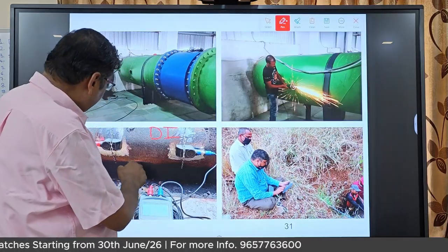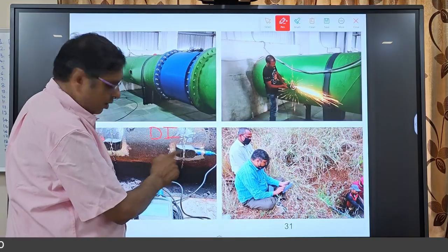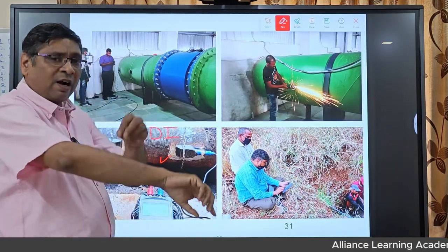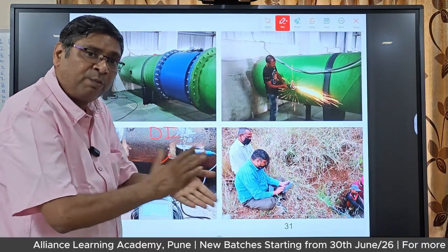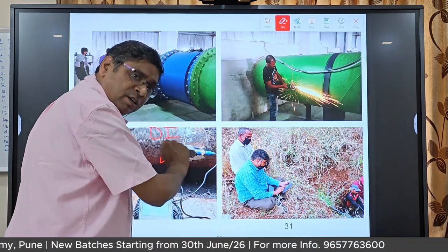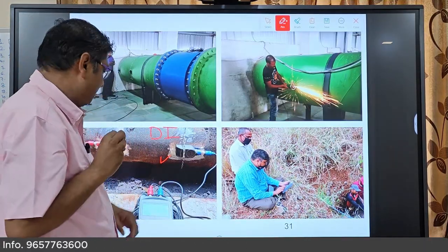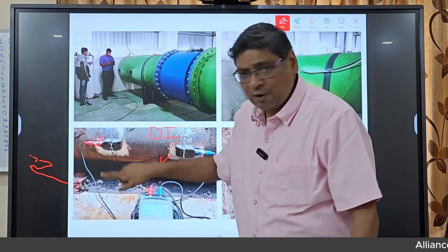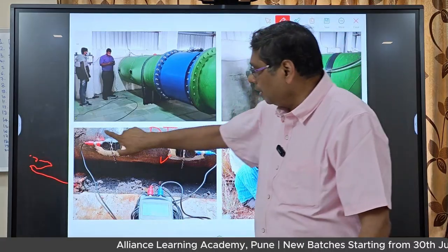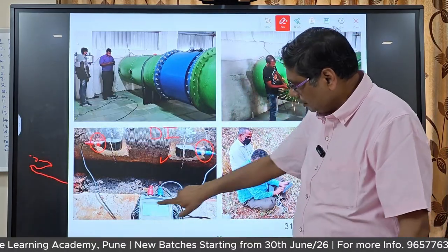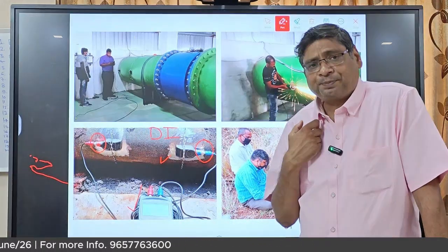So you see here, in a DI pipe, we cleaned it. See, this is a silver color, this is a black color. Then only will the ultrasound pass. So you take zero number emery paper and for at least 30 to 40 minutes you have to rub it and make it like this finish. Then only will it work properly. And there are two sensors. Here for the reference, which is the upstream or the downstream, the color is red, the other is blue, and this is its electronics where you see the flow.